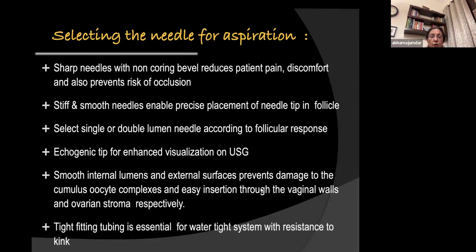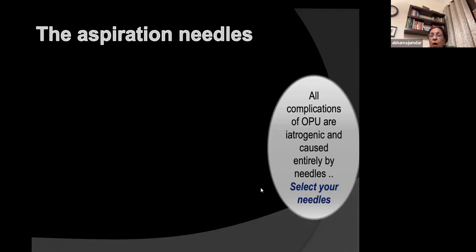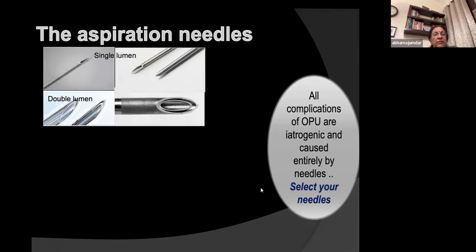Tight fitting tubing is essential for a watertight system with resistance to kink. So please, when you are checking, make sure when you've made all the connections, there's no kink in the system. It is an absolutely watertight system so that all the pressure generated through the pump is reflected to the tip of the needle. All complications of oocyte pickup are iatrogenic and caused entirely by needles. Entirely by needles. Whether you are able to pick up eggs or not, whether you cause bleeding, pain, or any injury to any viscera, it is all by needles. So select your needle very carefully.